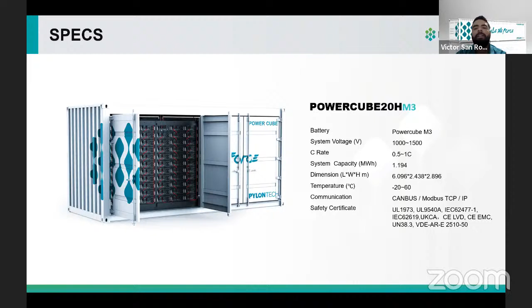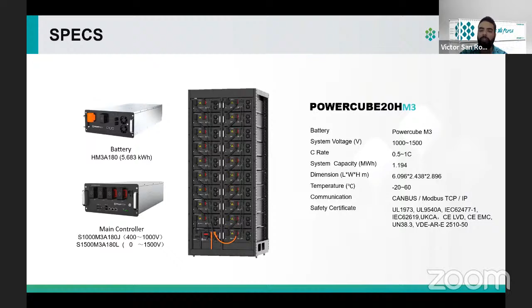This is the controller for these racks. The good thing about this type of battery is they can do 1C, so the batteries can charge and discharge in 1 hour, but they also have UL certification. And as they go into a container, they can be installed outside with no issue.